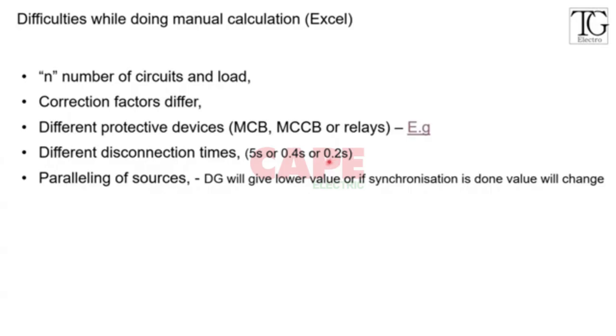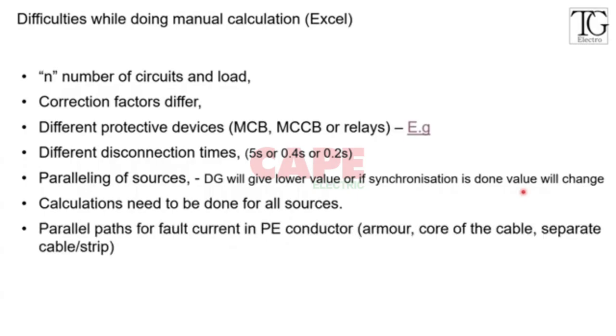The next problem you'll have while doing this calculation is if you have paralleling of sources, or if you're going to use a different source. Suppose you are using a DG, you will have different values, mostly lower values. And if you're synchronizing multiple transformers, it is again going to have some issues. It is going to have a much lesser loop impedance, and calculations need to be done at all sources. So if you have transformer 1, 2, 3, and DG, you have to do it for all the transformers and the DG.